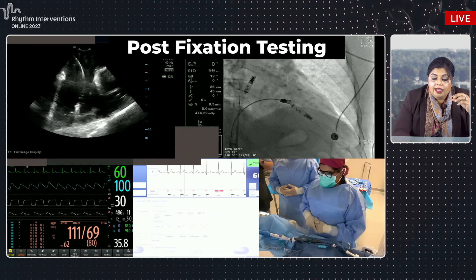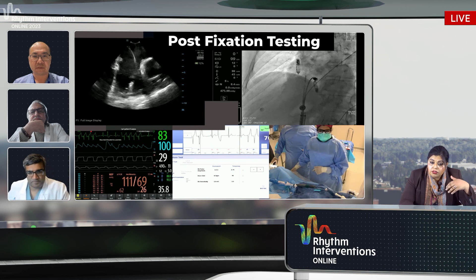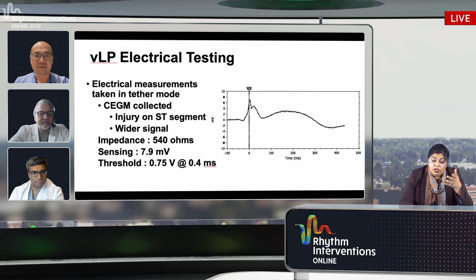And so once we have done our deflection tests and we're ready to do some post-fixation testing, we tend to see a pretty large injury current, usually after the implant or the active fixation of the helix. Again, because it's a broad base helix, so you expect a pretty wide injury current. Your R waves tend to go down. Your impedance almost always should go up. And your threshold could be pretty high just from the injury current. And here is a great example of how wide that injury current could be. Sometimes you can have a really high ST as well. Definite increase in the impedance, about 100 ohms. The R waves are slightly low. Threshold, surprisingly, was very good, even with this injury current, probably because of just being in a good location.